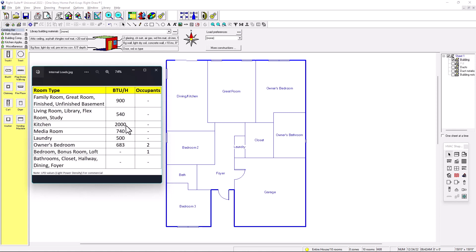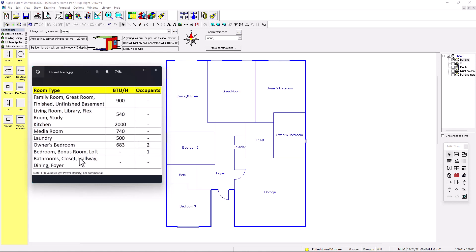For the kitchen, we'll put 2000 BTUs per hour. Manual J also suggests 1200 BTUs per hour, but to be conservative we'll use 2000. Media room in the basement is 740, no occupants. Laundry room is 500 BTUs per hour, no occupants. Owner's bedroom is 683 with two occupants — husband and wife, plus a TV. For bedroom, bonus room, and loft, we'll have only one occupant and no appliance load.